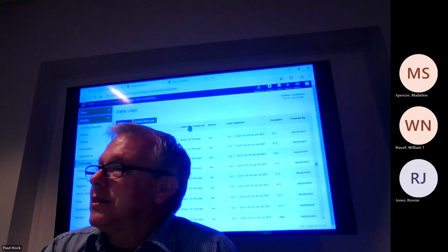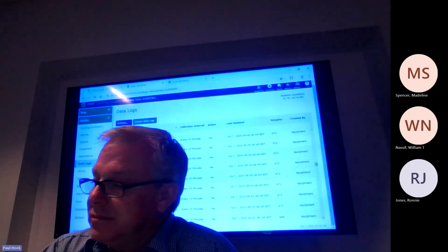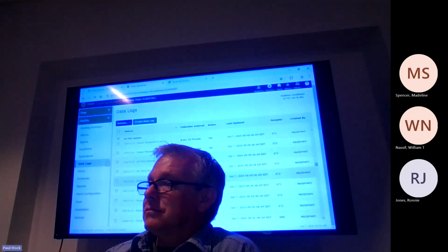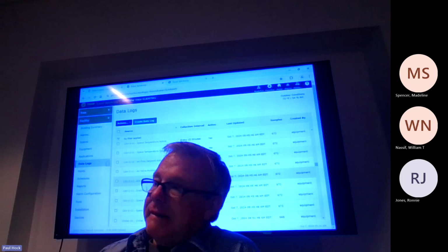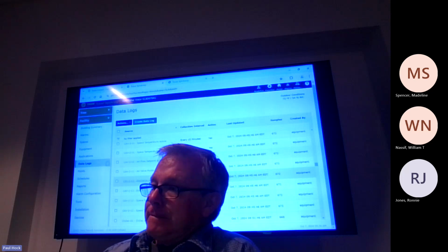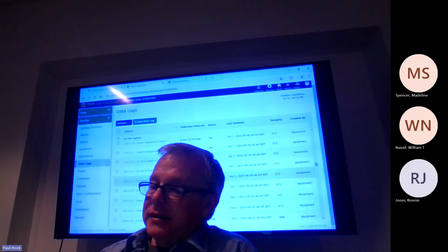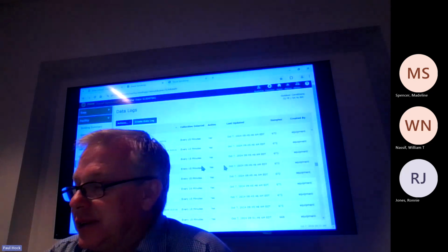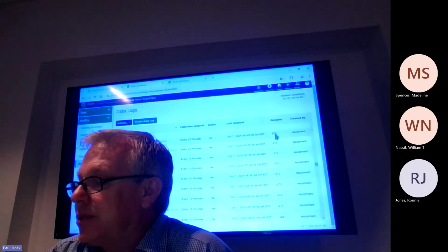Questions on that? Yeah, as an example, looking at the data you can see that we lost power, and you could see that spike. If you called Duke and they said we didn't have a power outage, I would assume that would be a major issue with the unit itself. Yeah, exactly. And this one here is only set up for a week's worth of data.